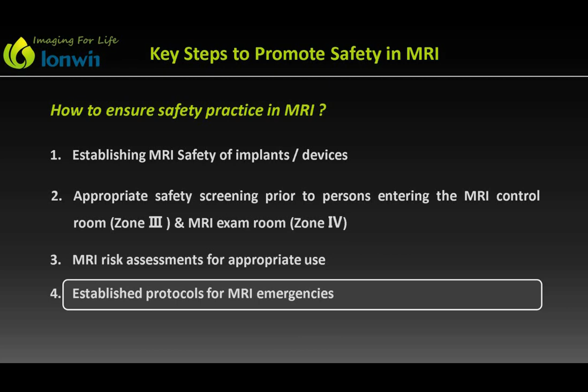Medical emergencies can occur in MRI. Ideally, a medical emergency response should never be conducted in the MRI scanner room. It's human nature to rush in to help, and people may inadvertently bring in medical items which are projectile hazards within the static magnetic field. For example, a wheelchair, defibrillator, or oxygen cylinder. You may remember this is what happened in the fatal case involving the young boy that we discussed earlier in this presentation.